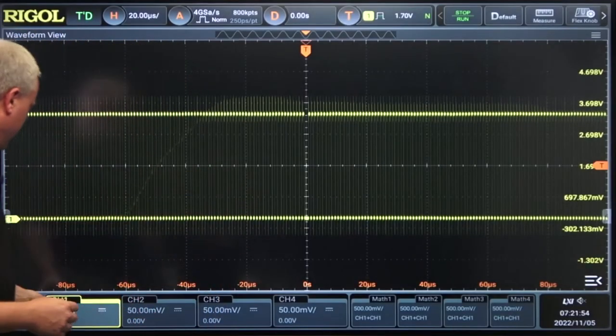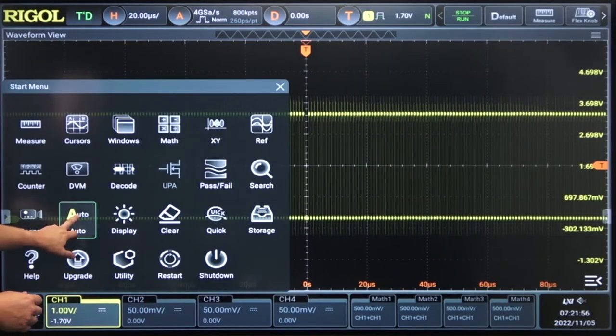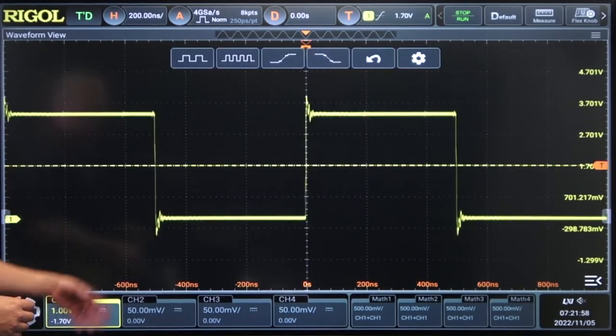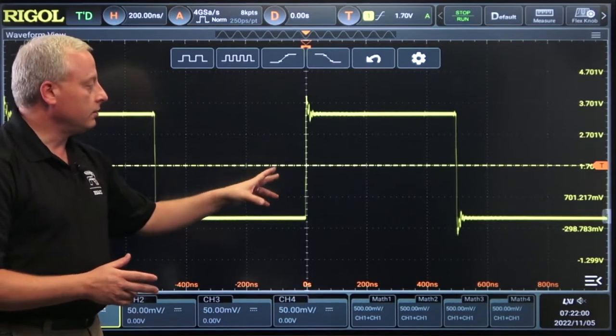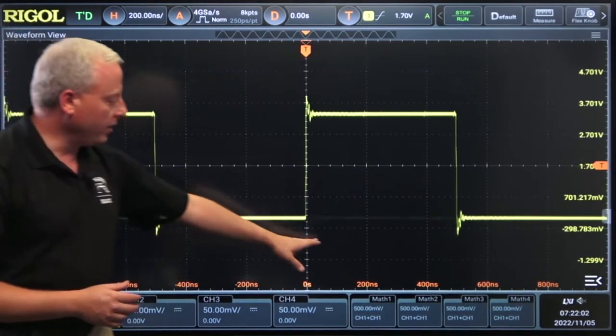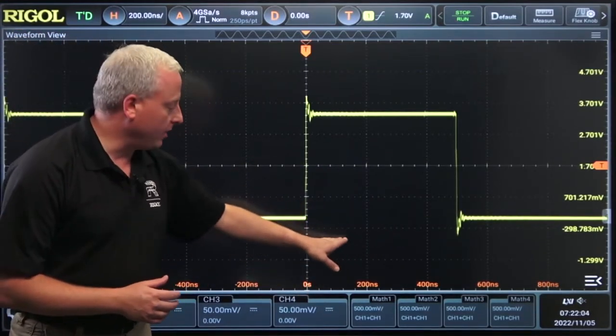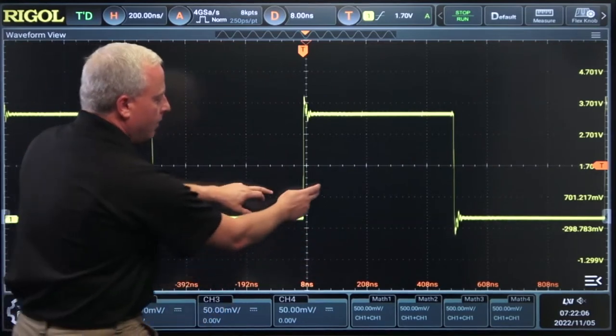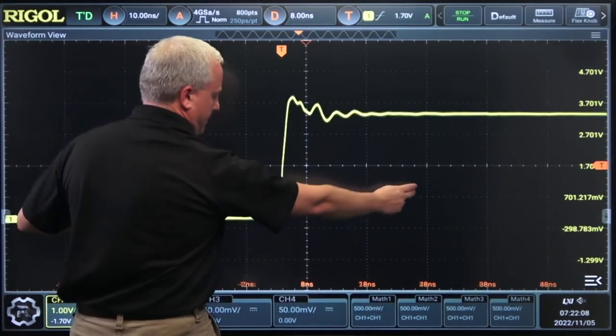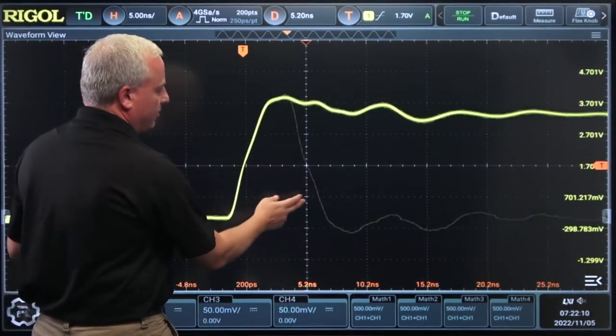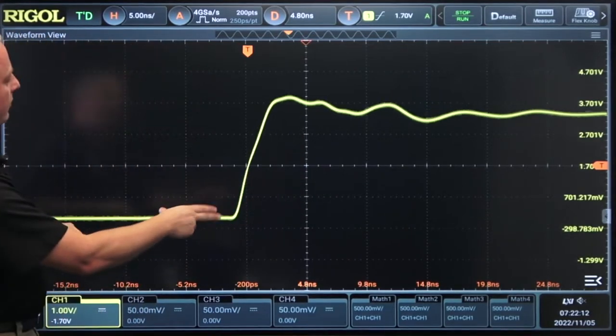We start with a signal on screen here. Let's go ahead and hit the fast auto. So immediately we see a close-up view of our signal come in. We can also see this dropout here. It's happening a few times a second. Let's go ahead and zoom in on that. So here we can see that pulse about 10 nanoseconds wide.